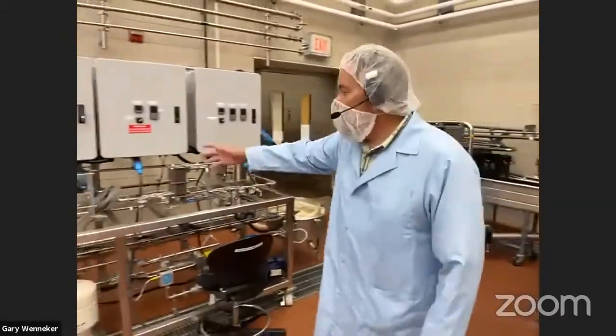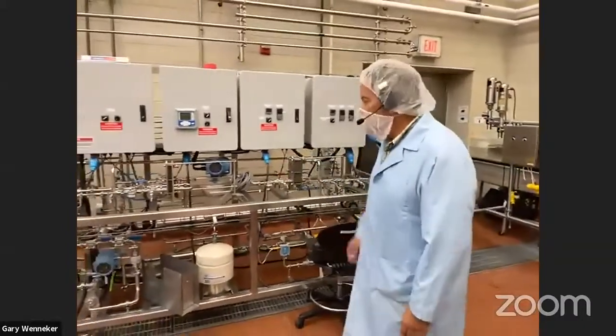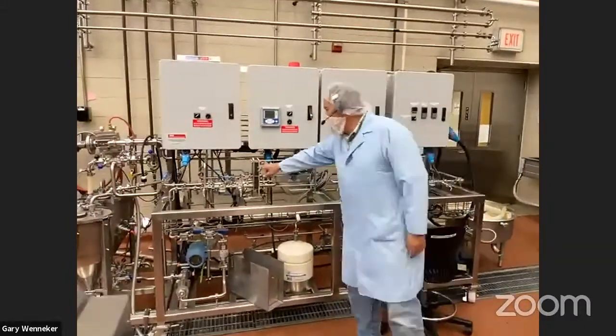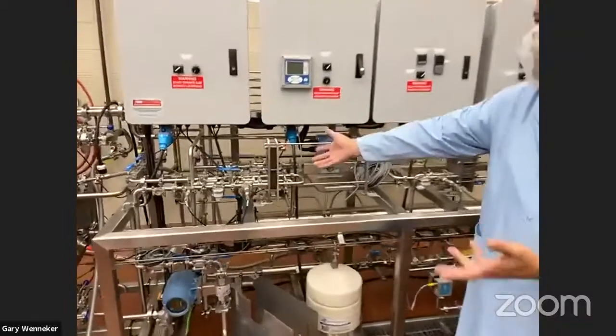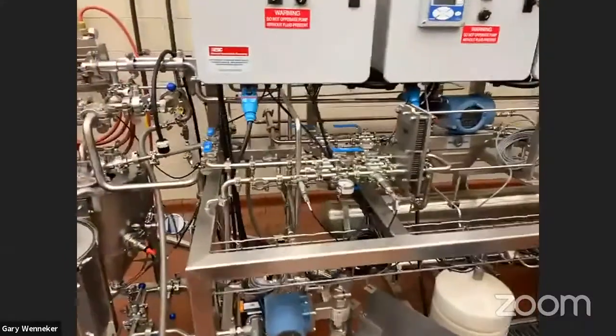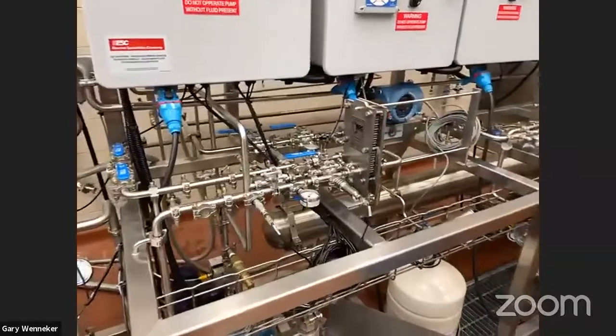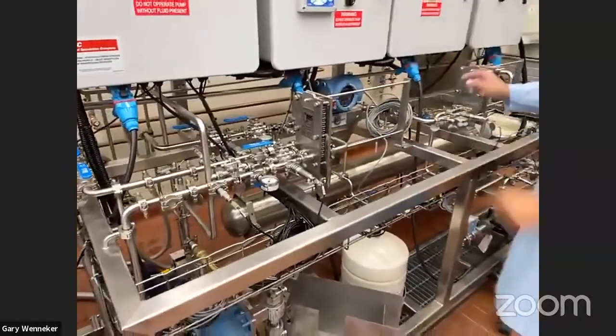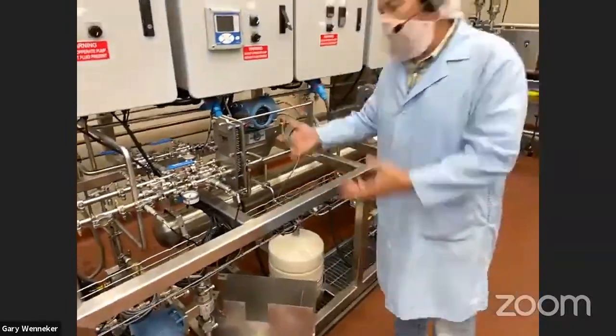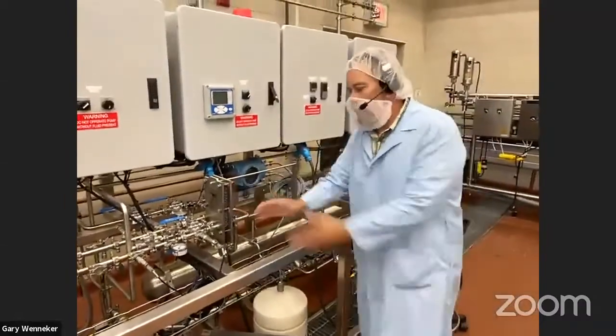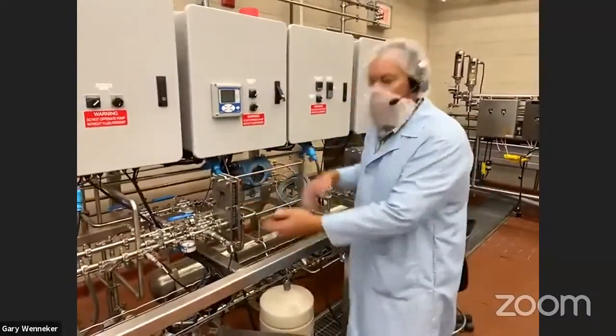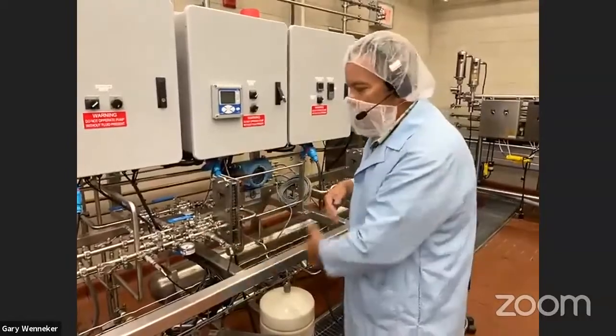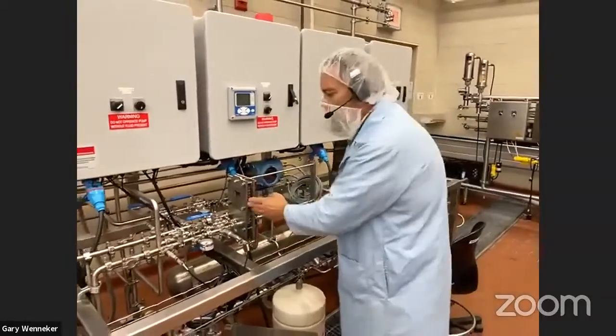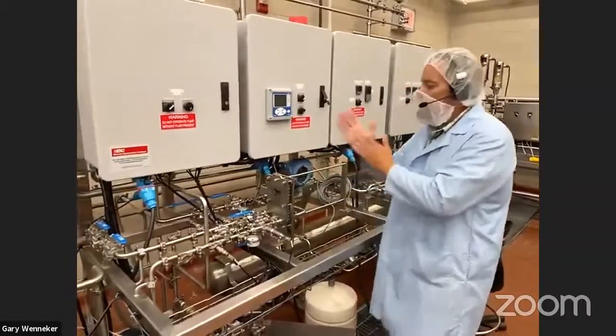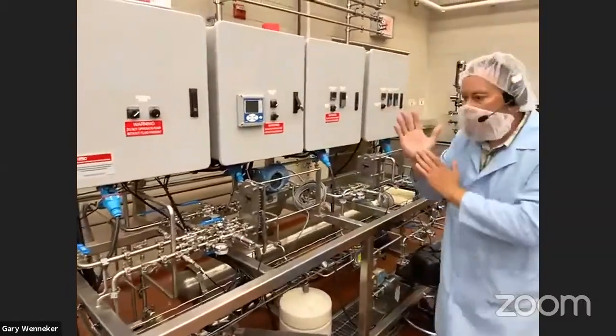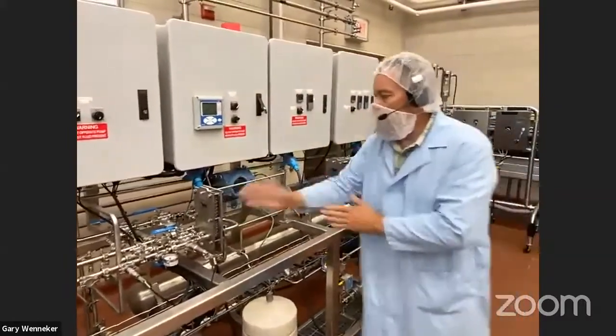Another piece of equipment we have is called a fouling skid. Once again, we have plate and frame heat exchangers. This can process pasteurized product, or you can do ultra high temperatures with these products. This machine was designed to measure fouling. Fouling is the amount of product that builds up on the plates as you process product continuously. So as you heat the product up on these thin metal plates, eventually you'll have what's called burn on, which is product that starts to stick to the heating plates.